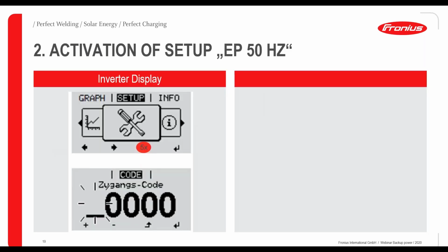Then the second step is we have to activate the emergency power setup. Basically, whenever you have installed the Symo Hybrid inverter, you first set up the date and time and the country setup of the inverter. So that's the first step. But then you need additionally to adjust the EP 50 Hertz setup, the emergency power setup.